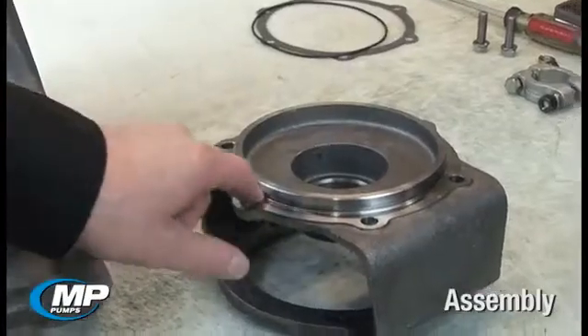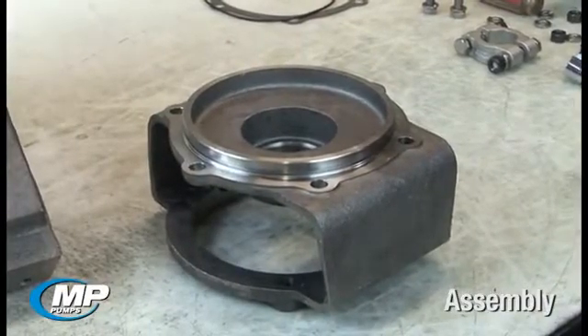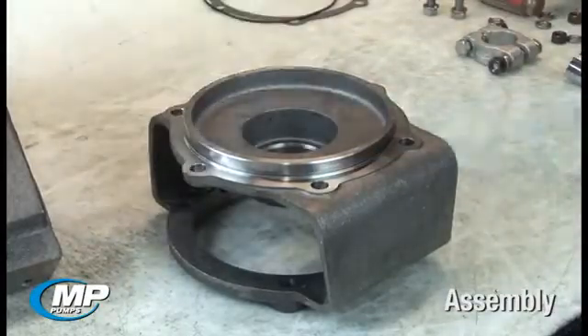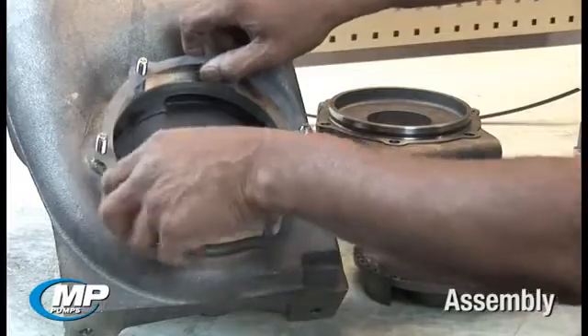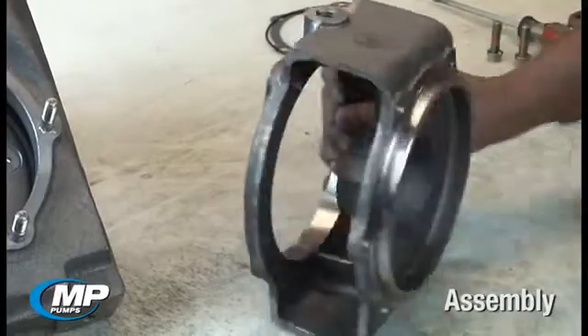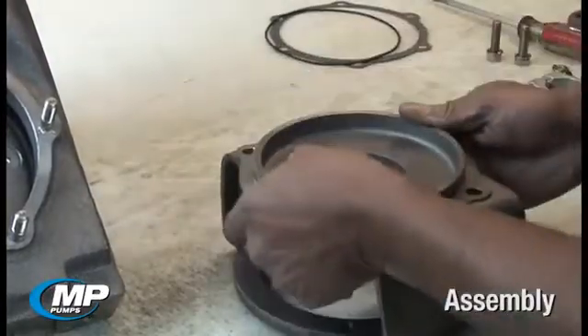The gasket area of the adapter should be inspected to ensure the sealing surface is clean and free of any corrosion or debris that would prevent the gasket from sealing properly. Inspect the gasket for any rips or tears. For a newer designed Flomax pump, you should also inspect the o-ring groove in the adapter to ensure it is clean and free of any nicks or burrs that may damage the o-ring and prevent it from sealing properly.